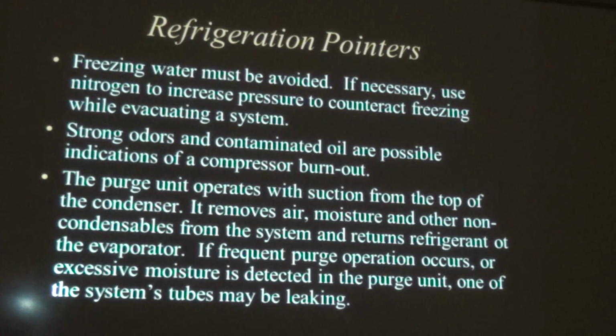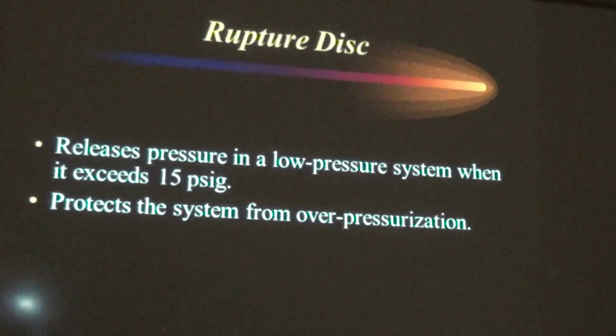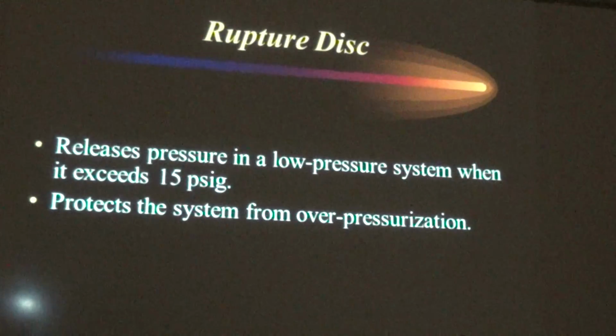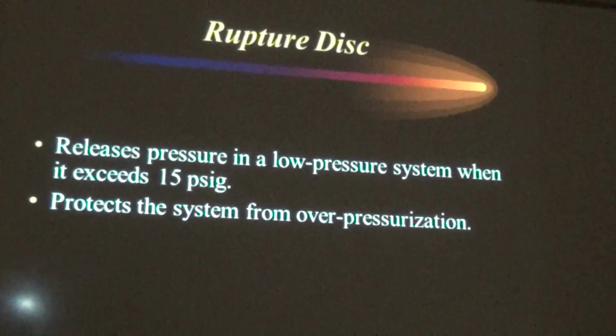Strong odors, again, indicate compressor burnout. The purge unit operates with suction from the top of the condenser. It removes air, moisture, and other non-condensables from the system and returns refrigerant to the evaporator. If frequent purge operation occurs or excessive moisture is found in a purge unit, one of the system's tubes is most likely leaking. The rupture disc releases when the pressure exceeds 15 psig, and it is there to keep the system from overpressurization.